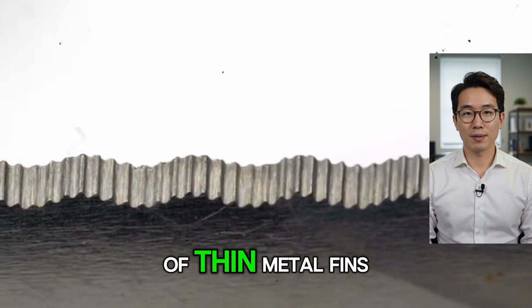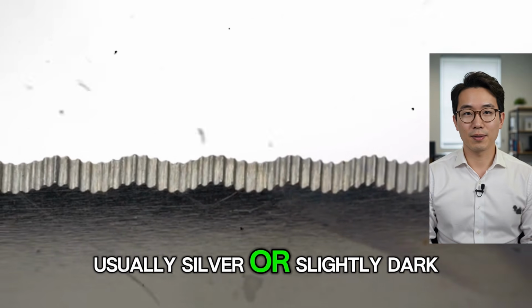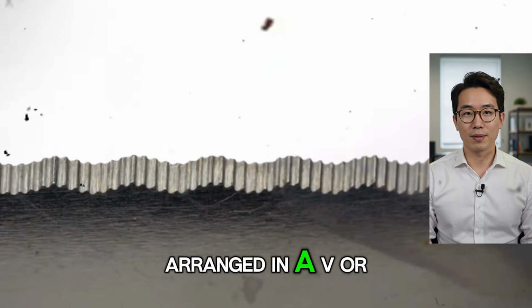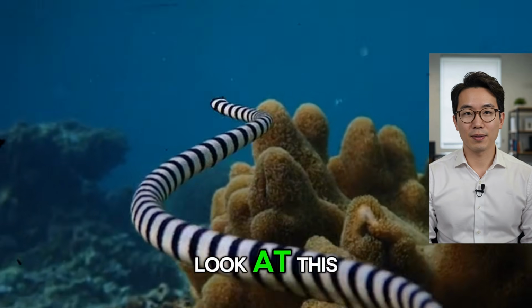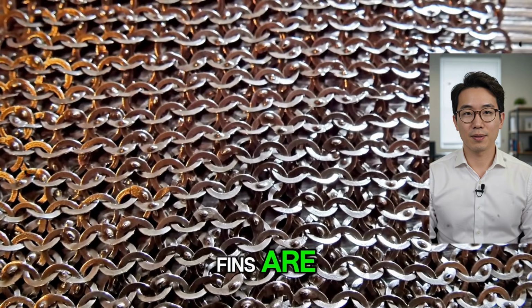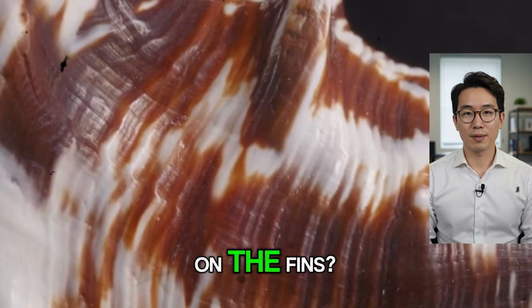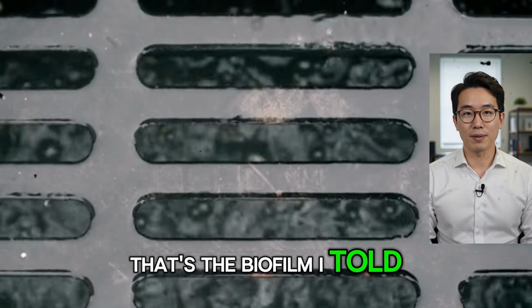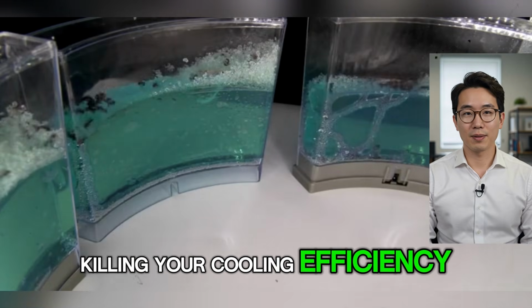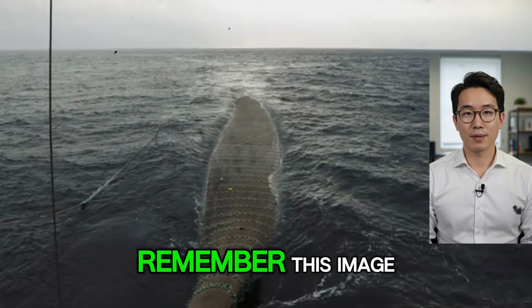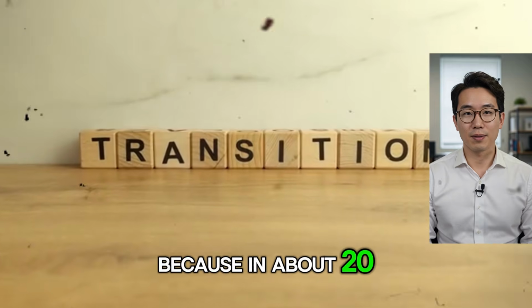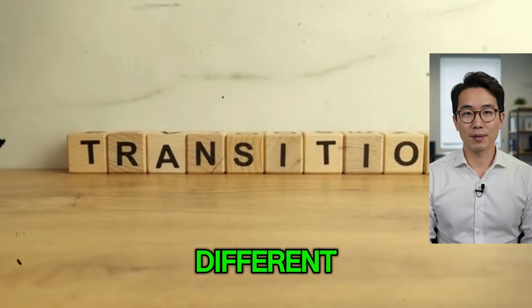It looks like a set of thin metal fins, usually silver or slightly dark, arranged in a V or A shape. Look at this. Look at how dirty these fins are. See that dark gray-brown coating on the fins? That's the biofilm I told you about. That's what's killing your cooling efficiency. This is before. Remember this image, because in about 20 minutes, it's going to look completely different.